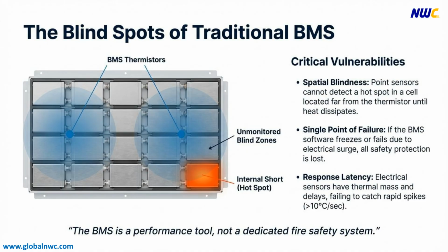Traditional BMS architectures rely on point-type thermistors, which create critical spatial blind spots beyond their limited sensing range. As a result, internal short circuits and early signs of thermal runaway occurring outside these points cannot be detected immediately. In addition, the potential loss of safety functions during software failure, combined with response delays caused by sensor thermal mass, further undermines the reliability of the system as a fire prevention mechanism. Ultimately, the BMS should be recognized primarily as a performance optimization tool. Its structural limitations make it inherently vulnerable when tasked with dedicated fire safety protection.